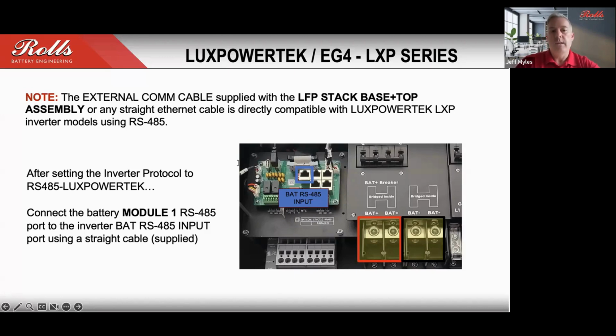So in the case of the LuxPower LXP series, you're going to be connecting the batteries to the RJ45 connection on the battery module 1. And out of the box, there is an RJ45 communication cable that's supplied. It comes with the base and top assembly, and that's your communication cable to the inverter. Now, it's a straight through cable, and that generally will work with a variety of different inverters. However, there are some brands that use a different pinout configuration than what is generally supplied in a straight through cable.